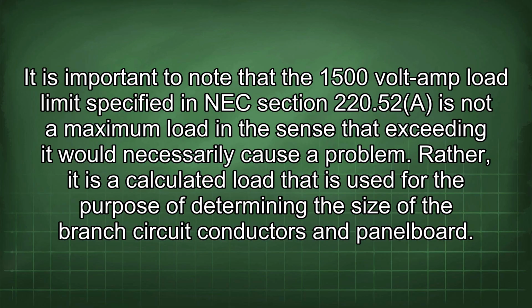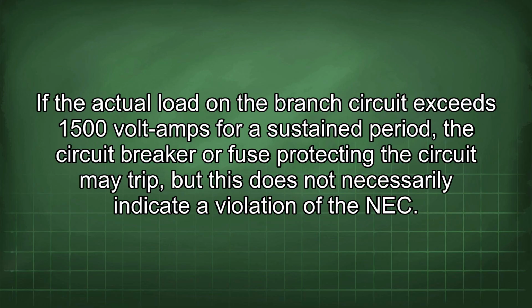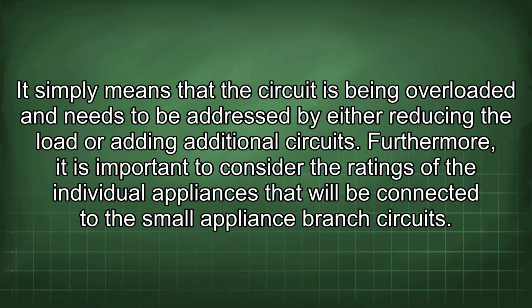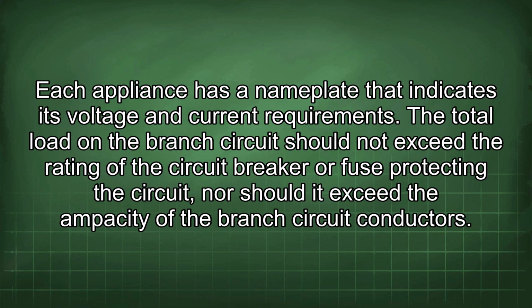It is important to note that the 1500 volt amp load limit specified in NEC section 220.52 is not a maximum load in the sense that exceeding it would necessarily cause a problem. Rather, it is a calculated load that is used for the purpose of determining the size of the branch circuit conductors and panel board. If the actual load on the branch circuit exceeds 1500 volt amps for a sustained period, the circuit breaker or fuse protecting the circuit may trip, but this does not necessarily indicate a violation of the NEC. It simply means that the circuit is being overloaded and needs to be addressed by either reducing the load or adding additional circuits. Furthermore, it is important to consider the ratings of the individual appliances that will be connected to the small appliance branch circuits. Each appliance has a nameplate that indicates its voltage and current requirements.